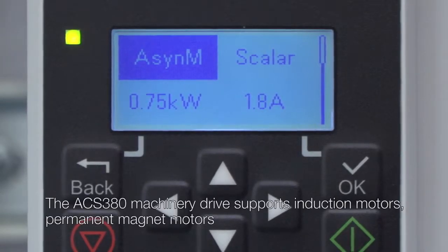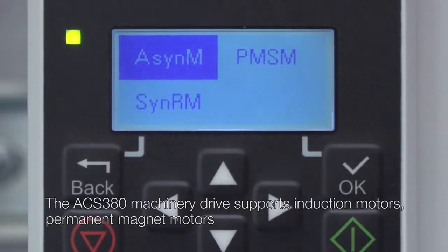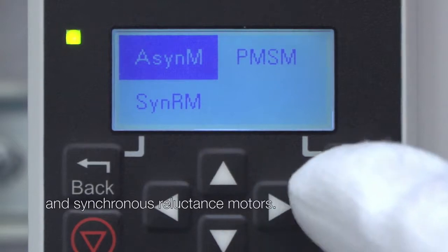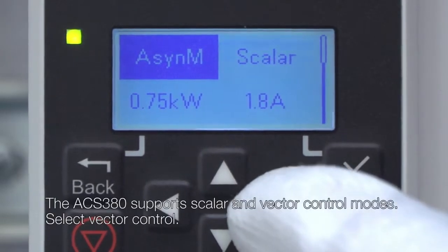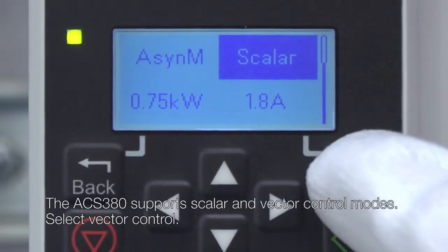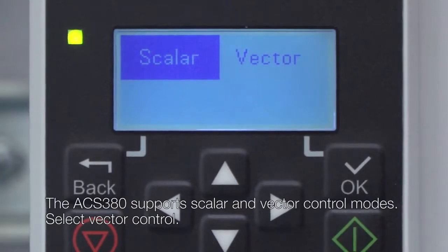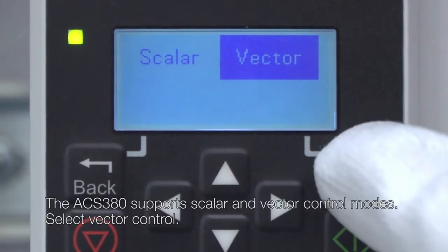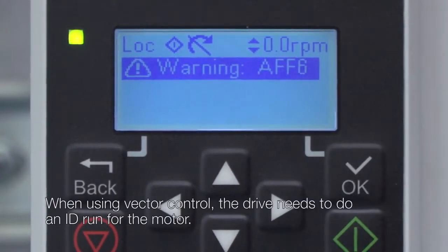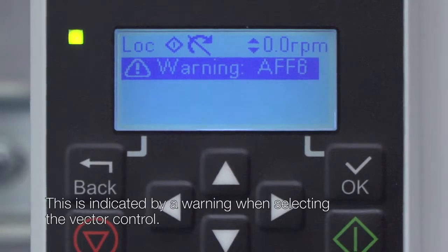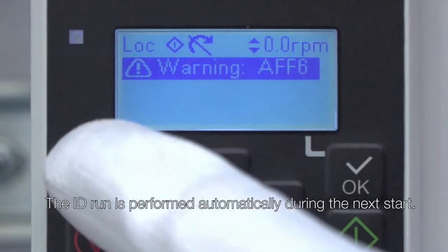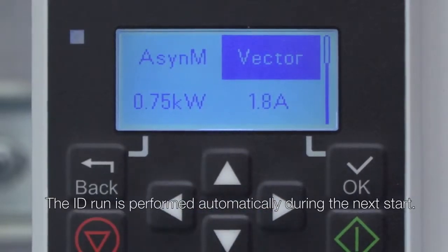The ACS380 machinery drive supports induction motors, permanent magnet motors, and synchronous reluctance motors. The ACS380 supports scalar and vector control modes. Select Vector Control. When using vector control, the drive needs to do an ID run for the motor. This is indicated by a warning when selecting the vector control. The ID run is performed automatically during the next start.